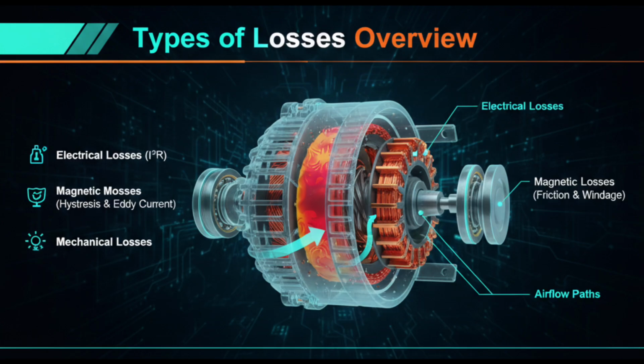Types of losses overview. In this slide, the alternator is shown as a cutaway model with different parts glowing to indicate heat generation. These glowing regions represent the main categories of losses inside the machine. Copper losses occur in the stator and rotor windings due to current flow. Iron losses occur in the magnetic core and are present even at no load. Mechanical losses are associated with rotating parts such as bearings and cooling fans, while stray load losses arise from leakage flux and harmonic effects under load.